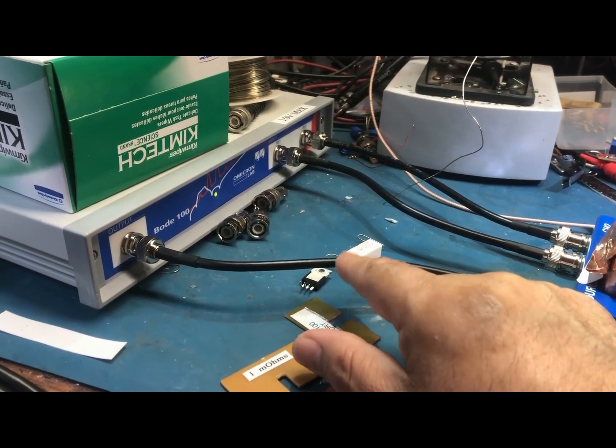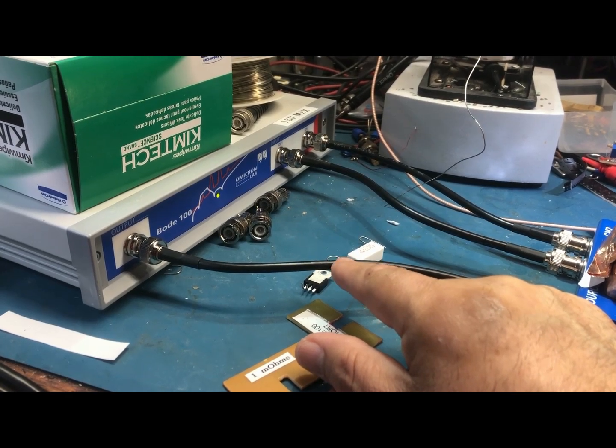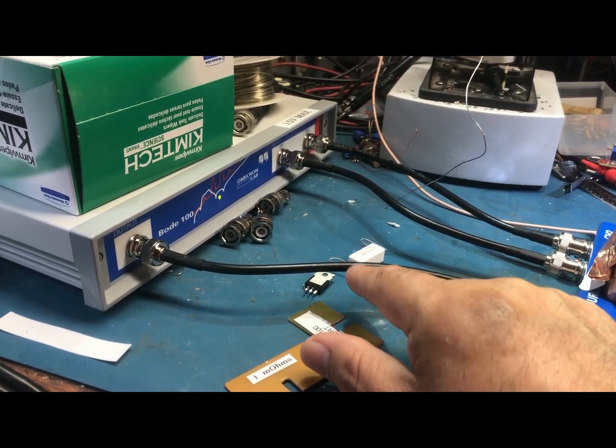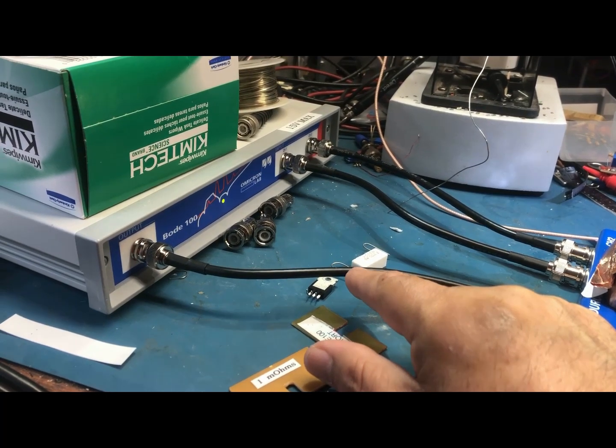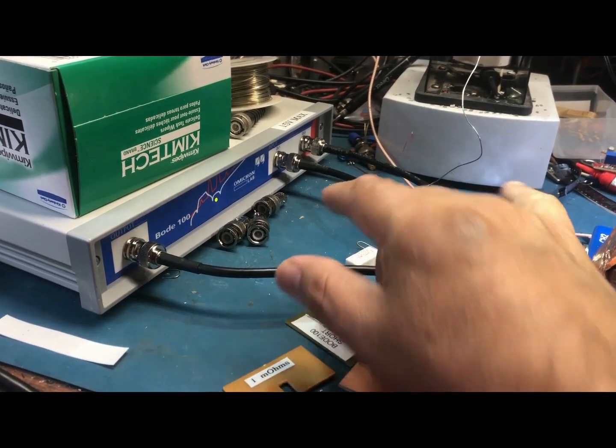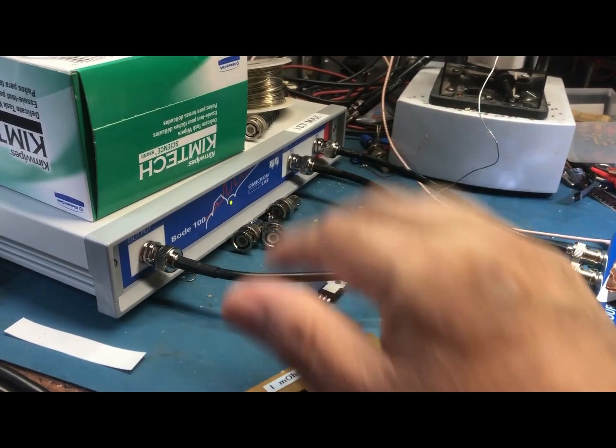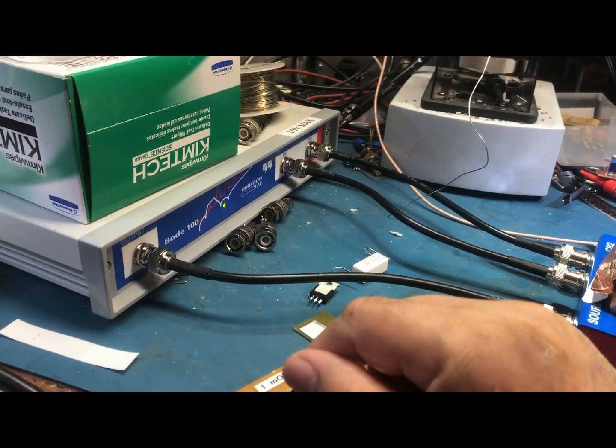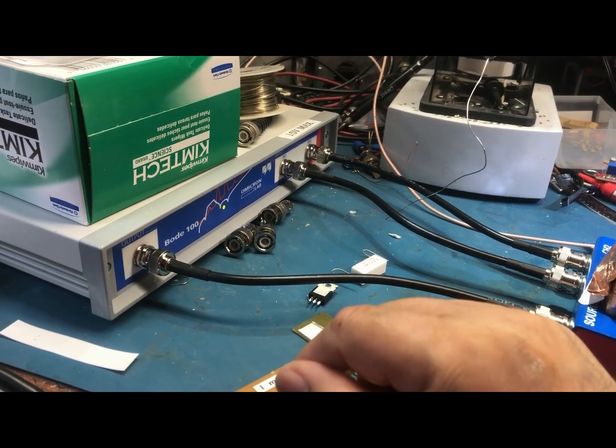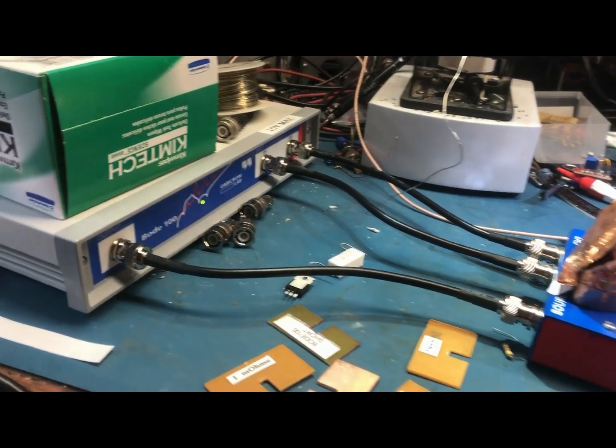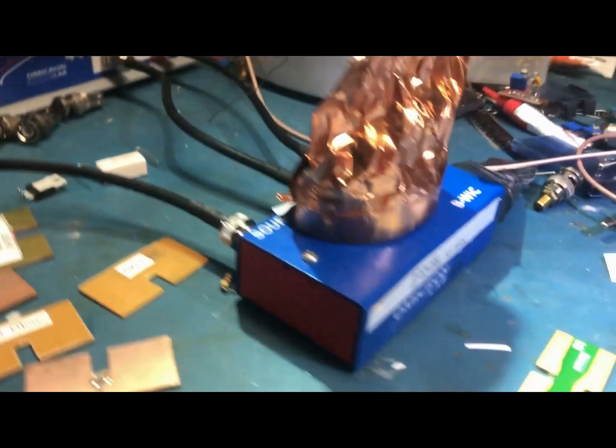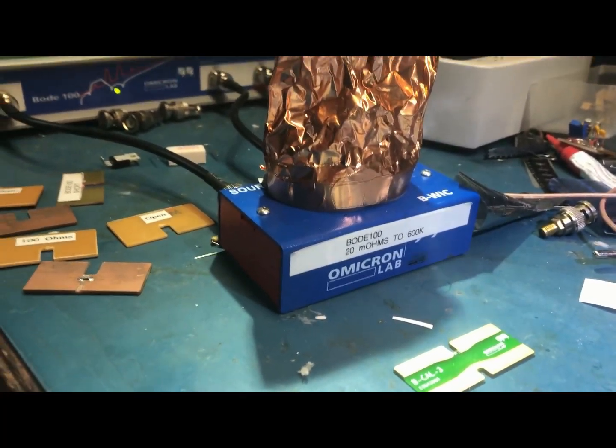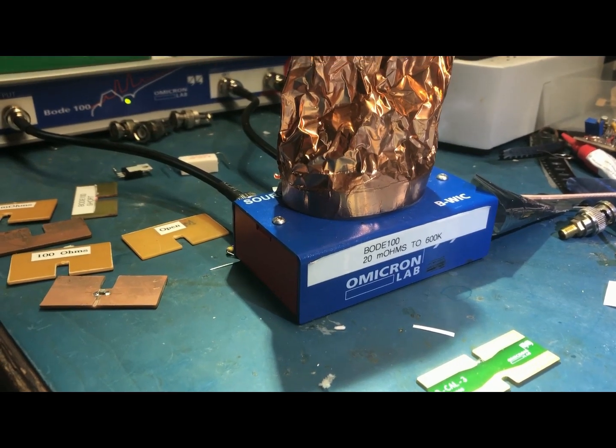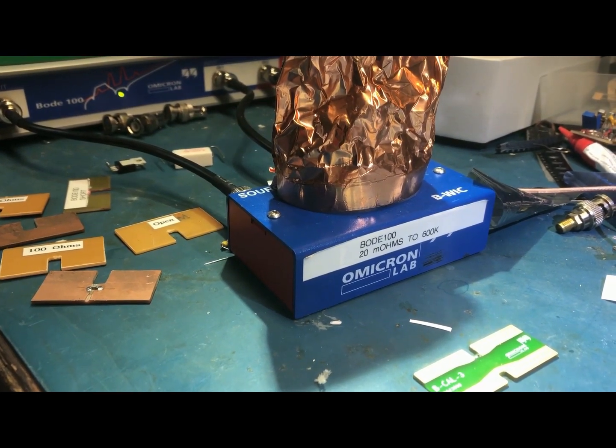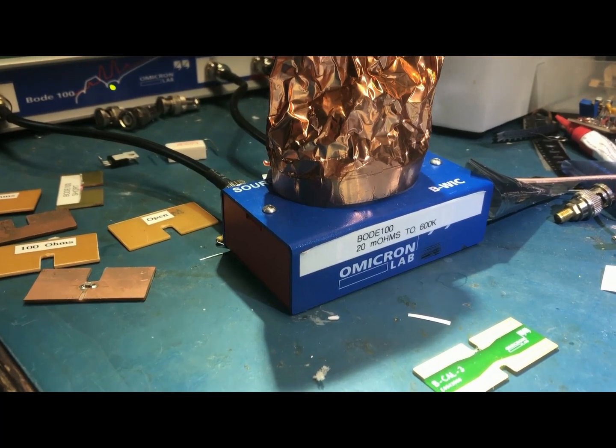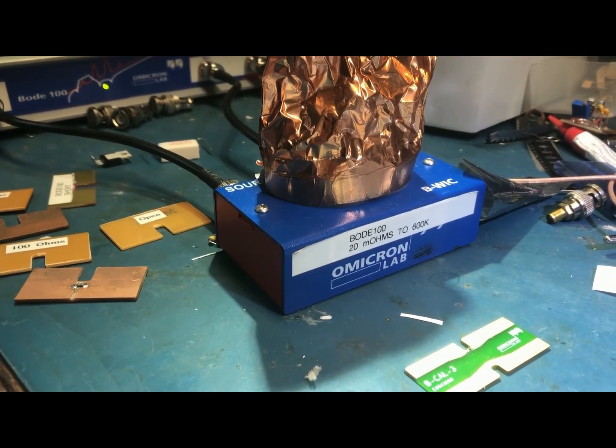There's an amp which will increase the voltage, and by increasing the input signal, it gives the Bode 100 more signal to use and make that measurement. So that's another option. But just by itself, even though this jig is specified to 20 milliohms, if you clean the contacts and maybe use the little shield, you can make measurements down to 1 milliohm comparably.